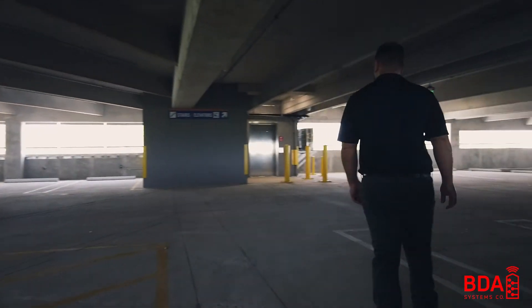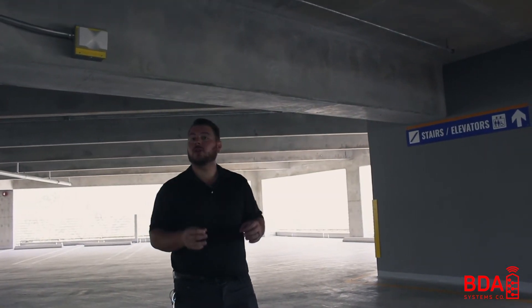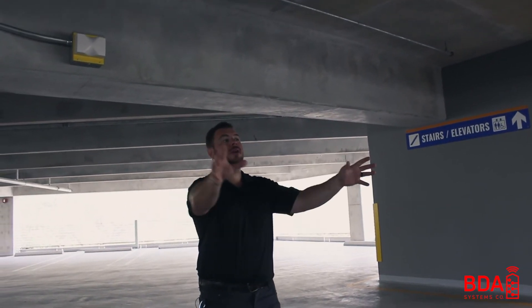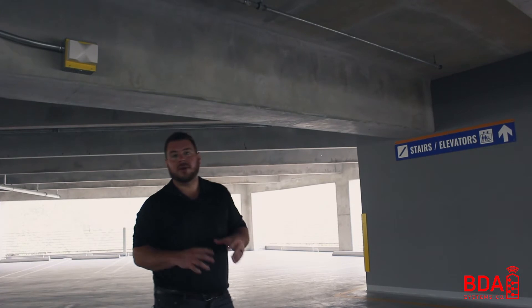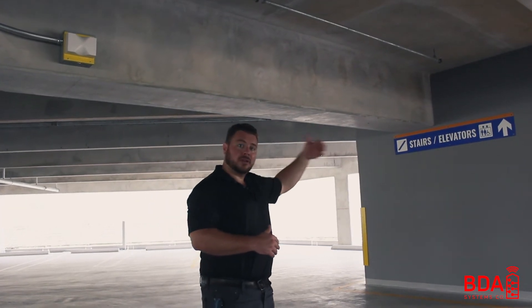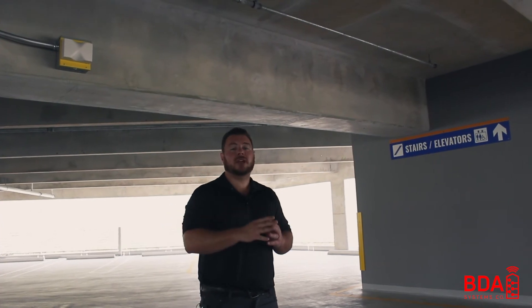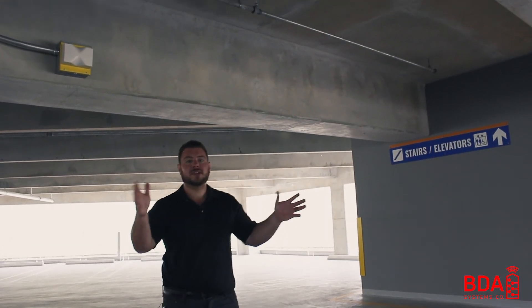Here's the directional panel at the end of the run on the second floor. It's right next to the stairwell and the elevator. This area uses a directional antenna with a 60-degree cone — 800 megahertz with 8 dBi directional panel. We have about a 60-degree cone sending a strong signal in the direction down the ramp, and it's also providing coverage to this side of the elevator and the stairwell. I'm not too worried about putting coverage right in front of it because this is the north side of the building where the donor signal is coming from the strongest. The other side of the building has the base station that's providing signal, and this antenna is just helping to match that — providing signal down the ramp and to the elevator and the stairs with a 60-degree cone, 8 dBi.